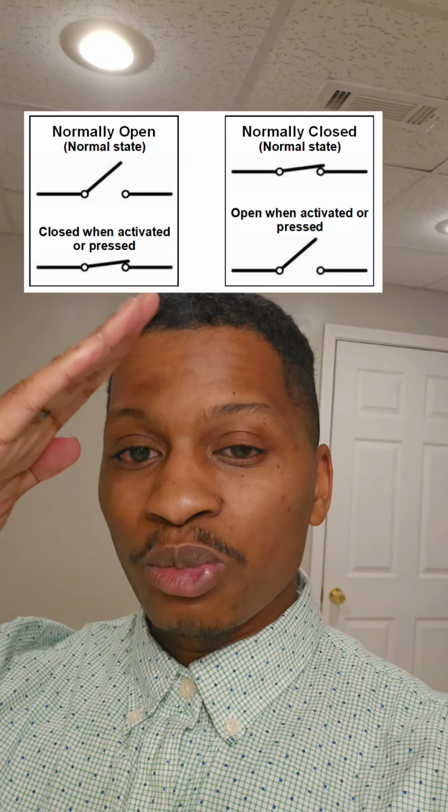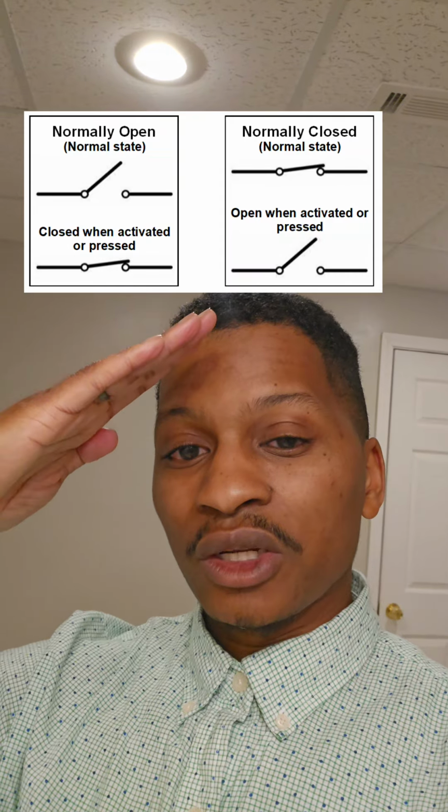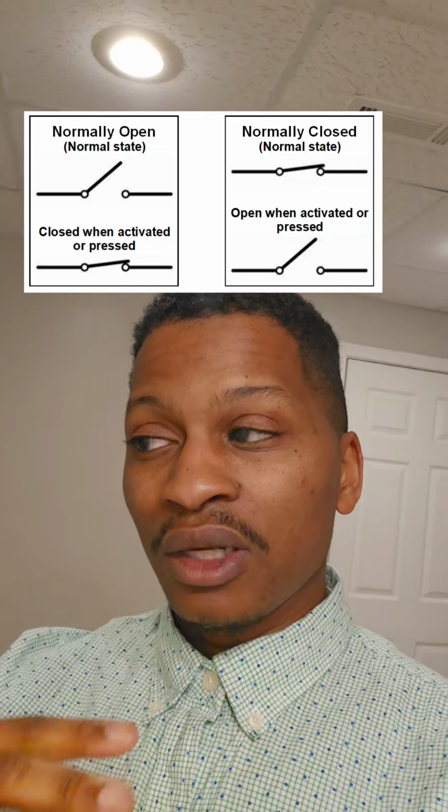Now, when whatever that sensor is tied to triggers, this normally closed contact opens up and that voltage goes away. So with your PLC or SCADA system, now it needs to trigger the alarm on the false status, because now it's at a logic 0. And same thing for the opposite. For a normally open contact, in its initial state, it's at a logic 0. It's in a false status. When the alarm activates, it activates on a true status, right, in your SCADA.